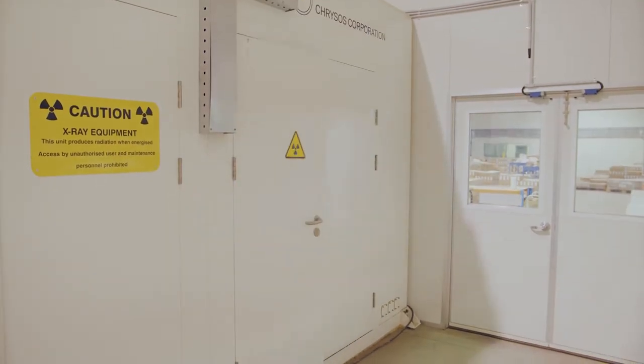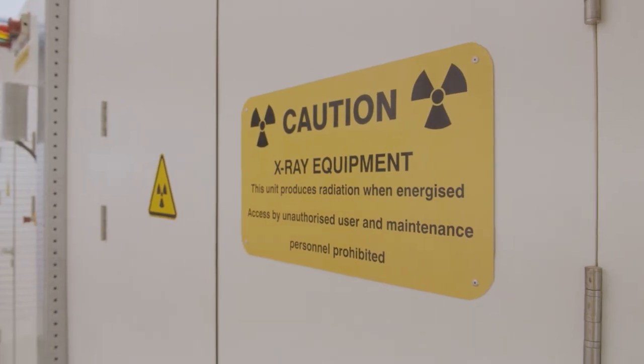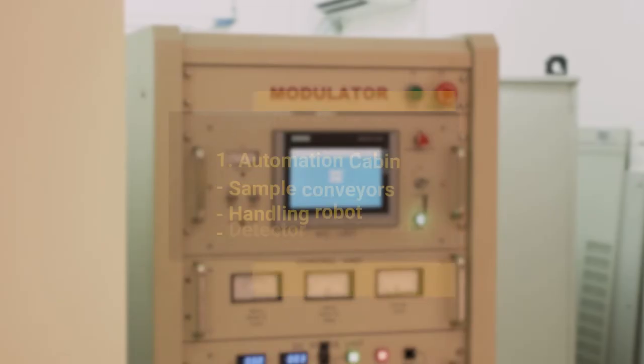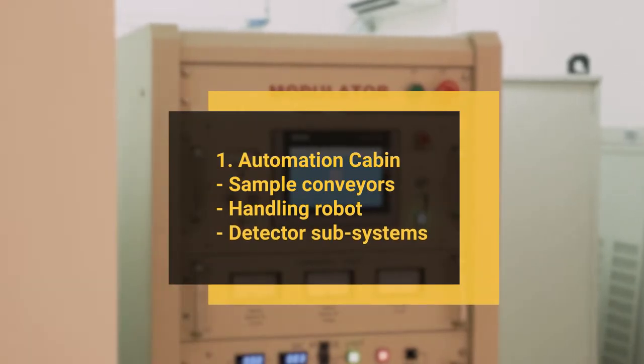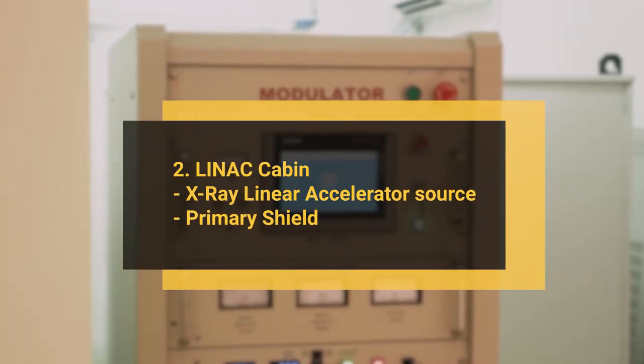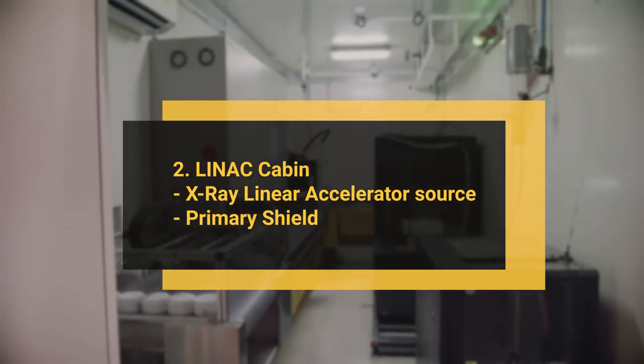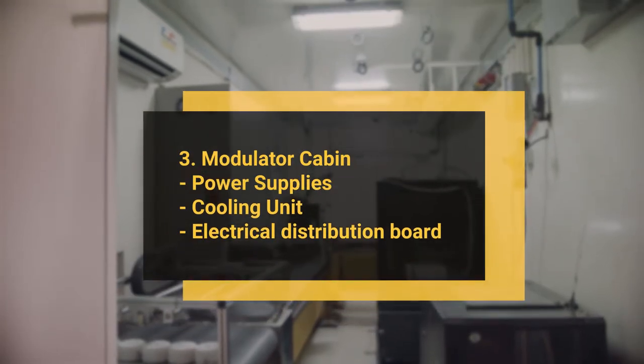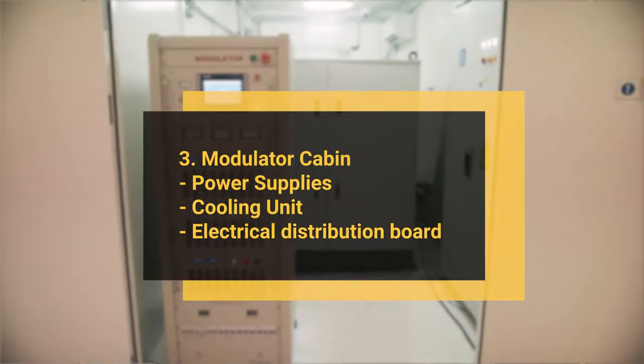The majority of the installation unit is housed inside three steel cabins, each the size of a standard shipping container. The three cabins are modular by design and can be factory commissioned then shipped to site, reducing on-site installation and commissioning requirements.